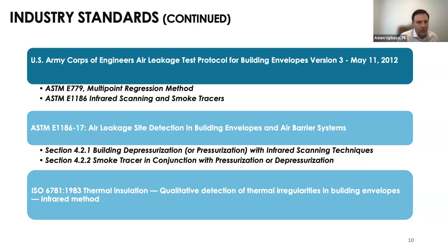ISO 6781, that's a standard that's often referenced. You see it on a lot of government projects. It's just a general standard method for how to perform infrared scanning. So you don't always see it. I threw it in here because it is commonly specified along with this test. It creates procedures so that whoever is doing the infrared scan is doing it properly, repeatably, and all those things.